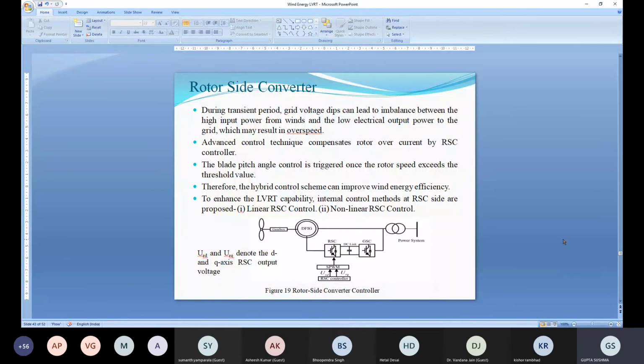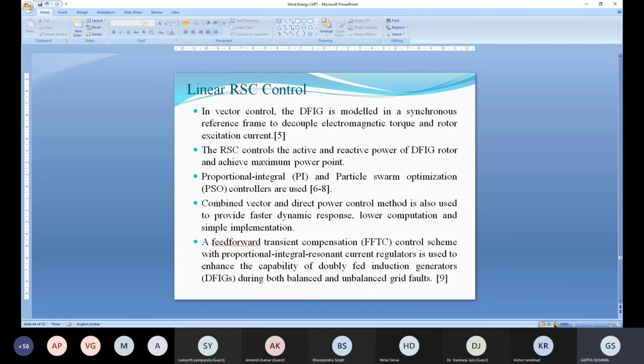The linear control methods which we can apply are: vector control method, proportional integral and particle swarm optimization PSO method, combined vector and direct power control method, and feed forward transient compensation method. These are the linear methods which can be applied at the rotor side converter, and we can control the current as well as voltage to keep the DC link voltage constant and protect the rotor from overcurrent. These are the control techniques through which you can control the reactive power and active power at the rotor side as well as the DC link. So these are the linear methods.